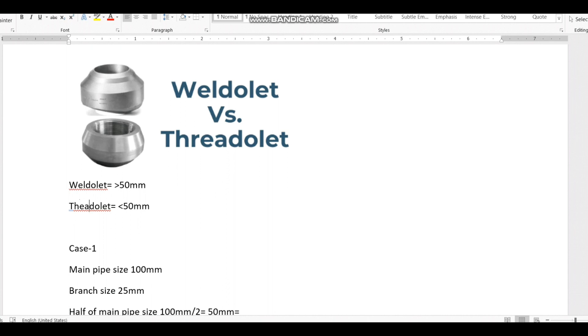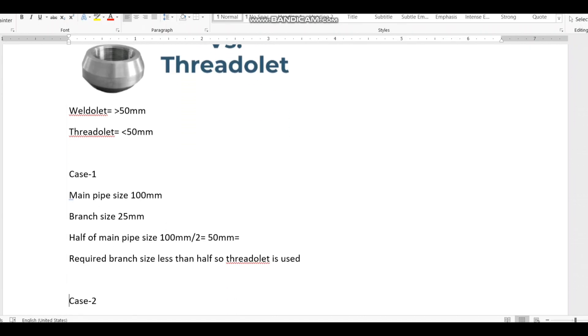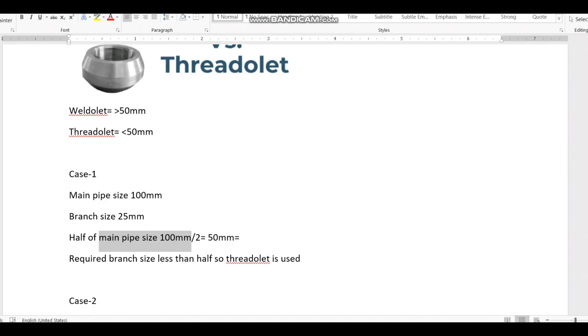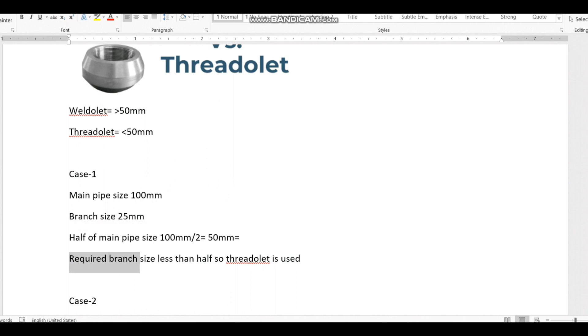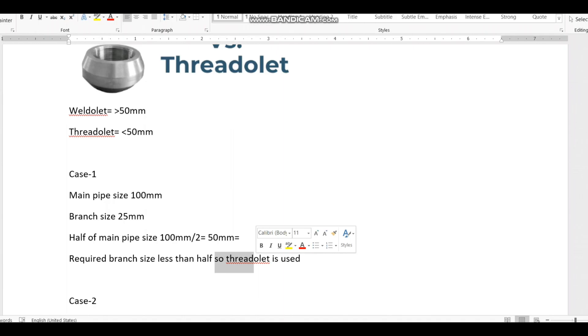A weldolet can be used for taking a branch greater than 50mm, and a threadolet can be used for branches less than 50mm. Case one: the main pipe size is 100mm and I want to take a 25mm branch for one FCU. Half of the main pipe size is 100mm ÷ 2 = 50mm. The required branch size is 25mm, which is less than half the main pipe size, so I can use a threadolet connection — no need for a reducing T and reducer.